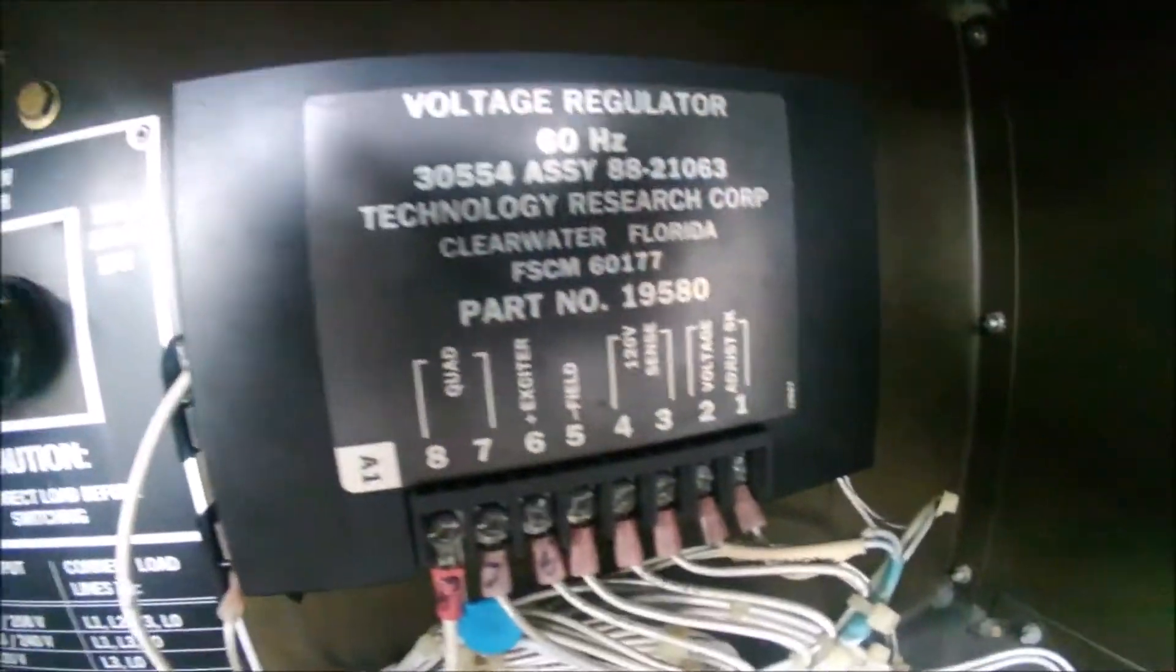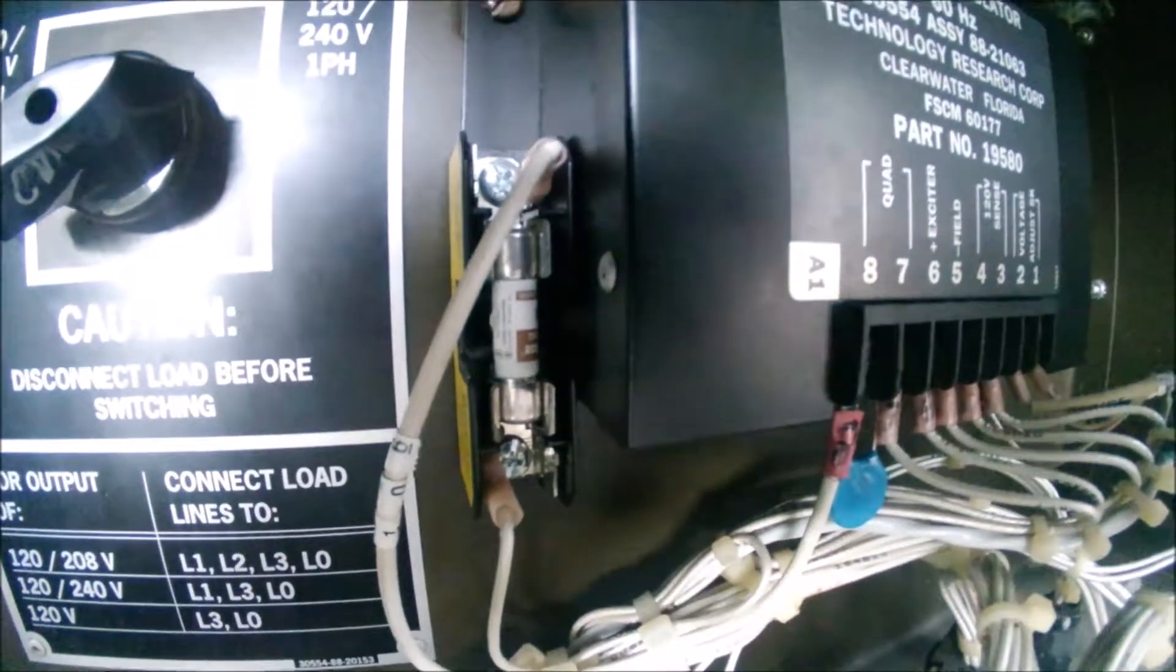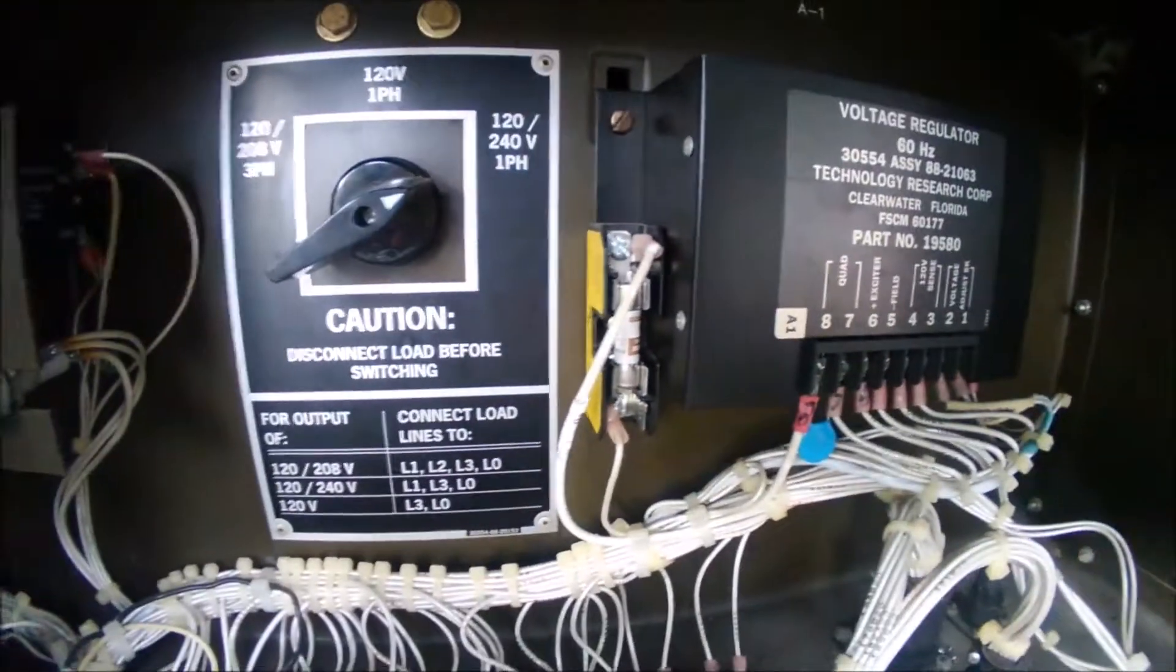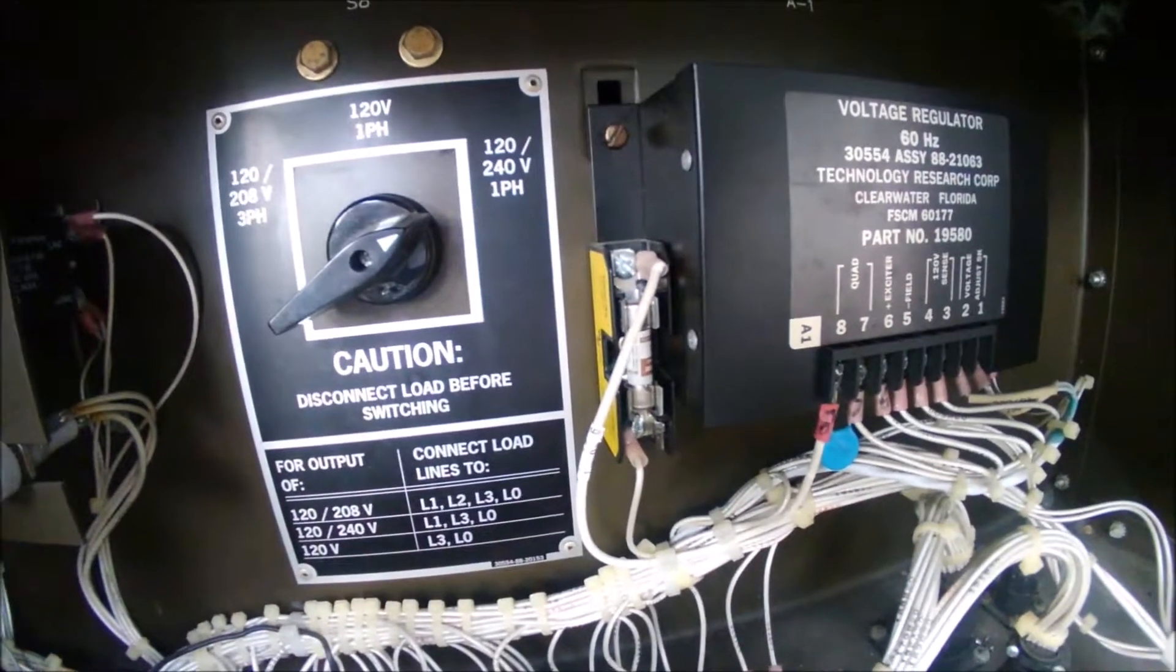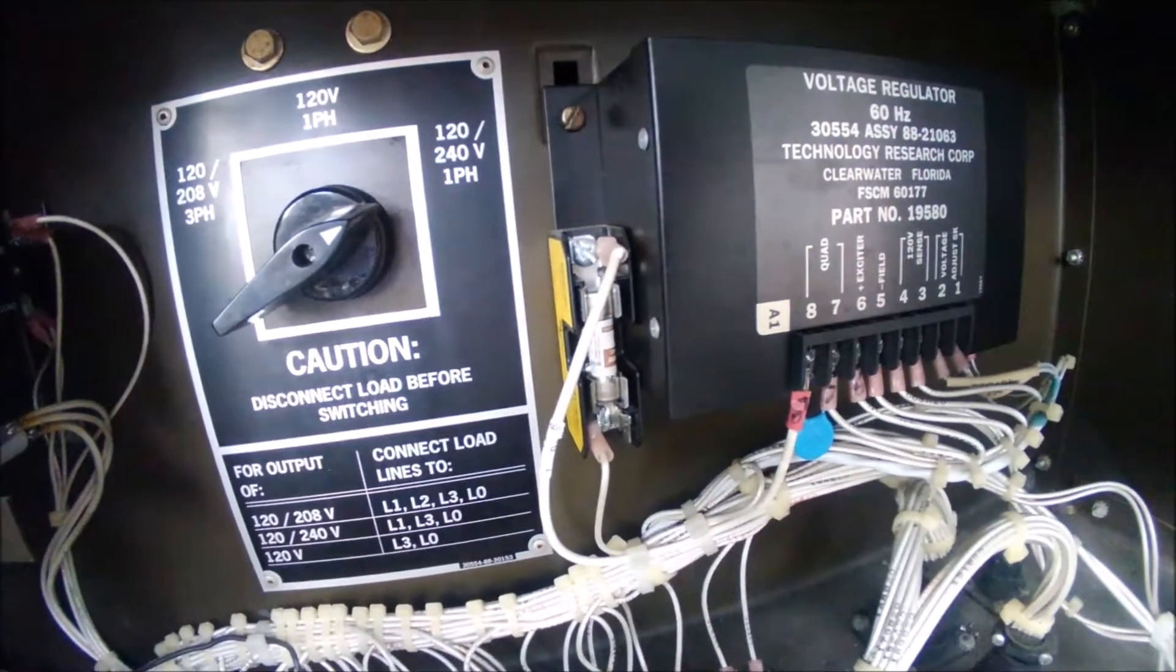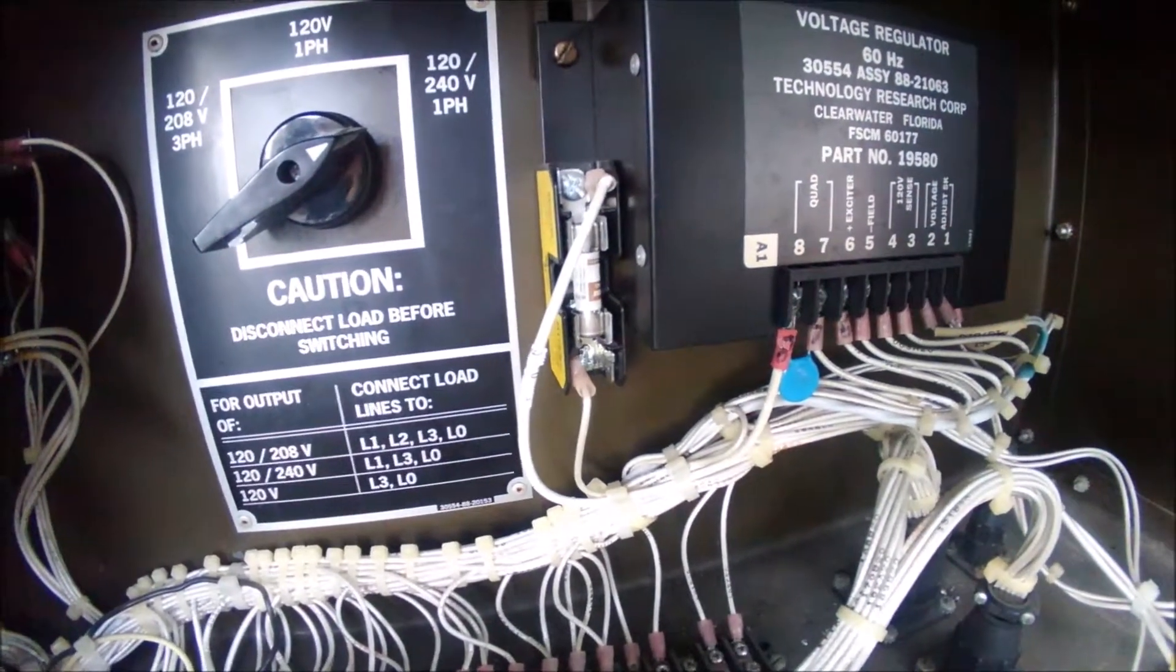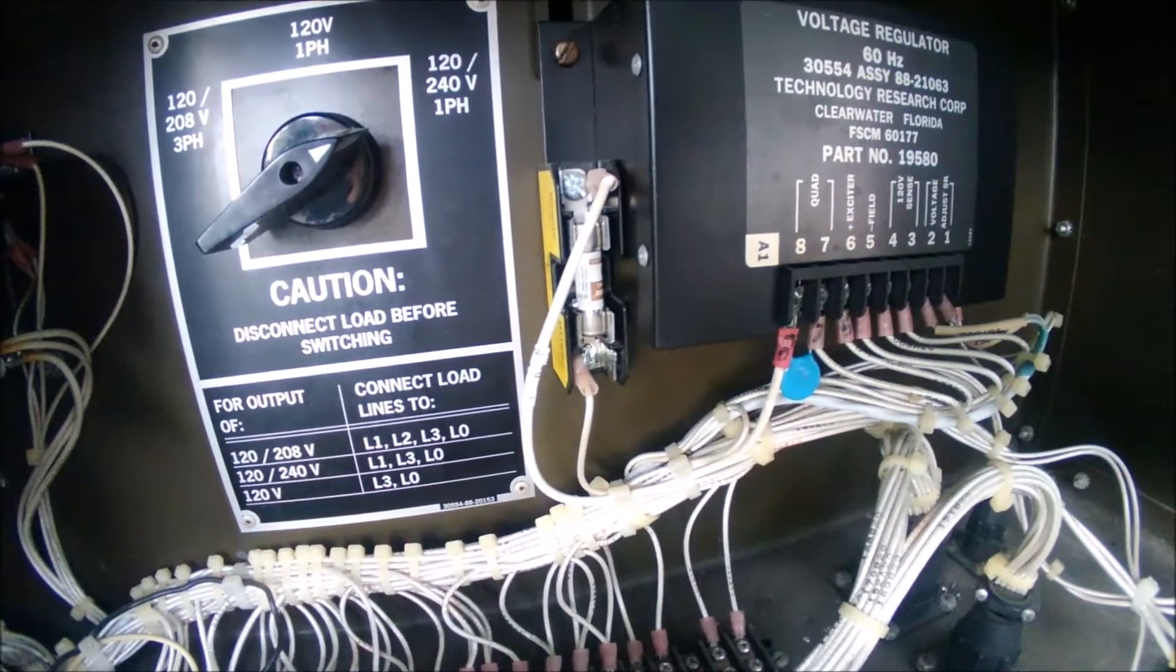Over here is the voltage regulator. You can see mine has this little fuse holder on the side that's put in line, and also this little blue disc. The fuse holder on the left-hand side is called the excite circuit fuse modification. This was actually directed to be put in starting around 2009 or 2010 for issues with troubleshooting the stator.